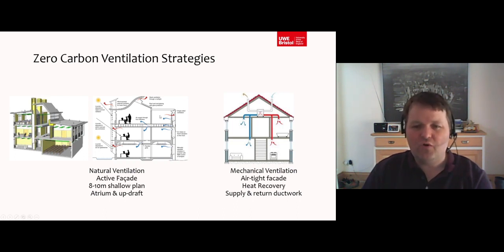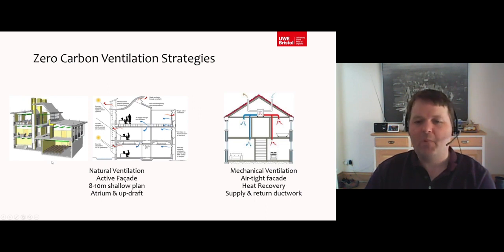And so yes, you could draw air longer distances than 8 meters, but that's very experimental and very rare. Much more common is actually just to have an atrium in the middle and be drawing it through the atrium, and then if you get an issue, you might have to extend the length of these up into the air if you need a situation where you have to draw particularly more air through one of these buildings. So that's natural ventilation, very active facade, drawing air in from the outside, but very low energy because we've reduced the need for a fan moving the air around most of the time.